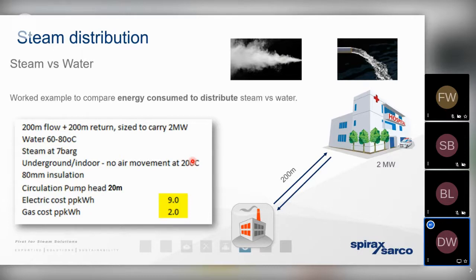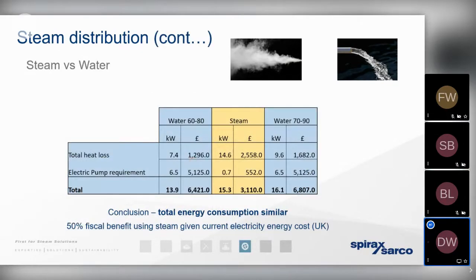So just to put that in further financial terms, we've got a chart here that is comparing steam to low temperature hot water with a 20-degree delta T, 60 to 80, and the same delta T, but at typically higher conditions, 70 to 90. As you can see, straight away, we've recognized that the cost of gas is going to be significantly greater to produce steam than it is to produce hot water in each of the examples. But when we add in the electrical requirements to satisfy those circulating pumps, you can see that the cost benefits of producing water are significantly diminished. And in fact, it's more attractive to compare steam.